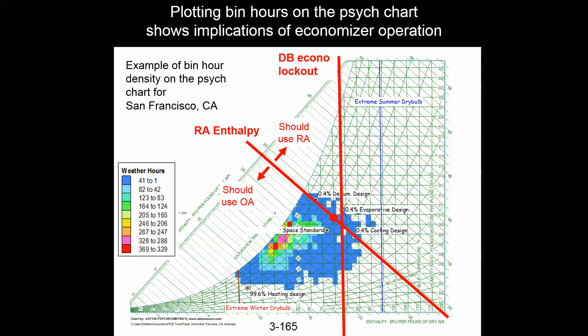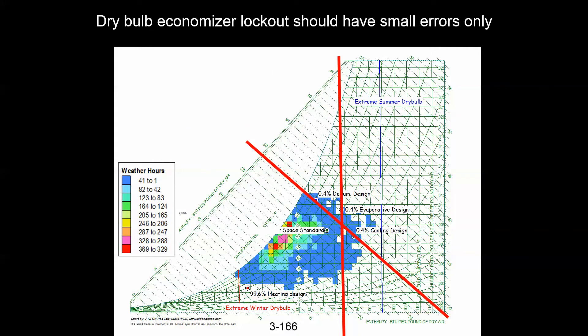Because dry bulb temperature sensors are more reliable, we select an economizer lockout that uses outside air below a specific dry bulb line and return air above it. We'll have some errors — there are cases to the left of the constant dry bulb line but above the constant enthalpy line — but this is the compromise of using wet-bulb-based conditions to select a dry-bulb-based economizer lockout.